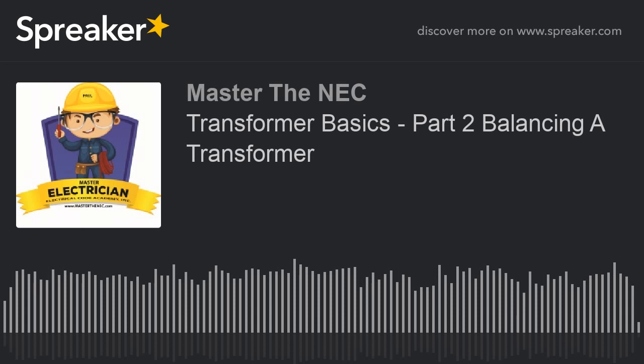And so since it could be an issue, we want to equate a little bit more VA on that in order to be able to do that calculation. So in my case, I might put it at 7 on A and 7 on B. So I'm actually taking this one as if it was a 14 kVA versus a 12 if I'm dealing with this situation. But let's just keep it at the values we have for calculation purposes and the ease of working through our calculation.